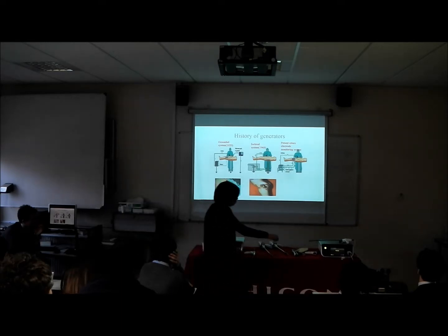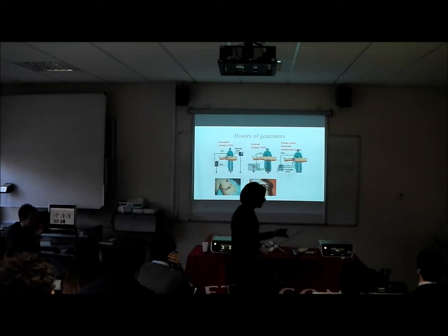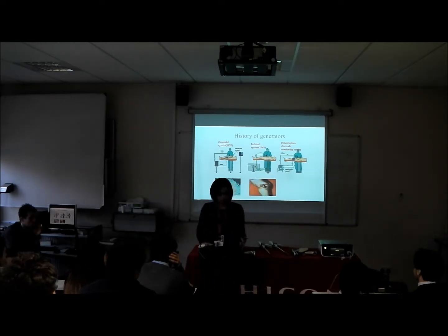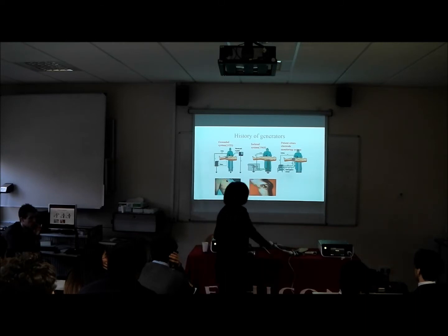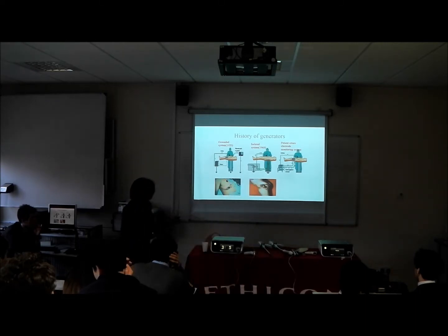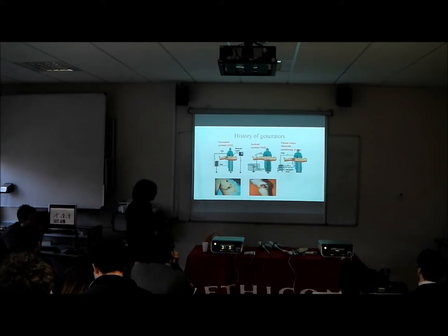That's why the tip of this equipment is really narrow, so that it's precise. Let's say you want to burn this area, you just attach it here. So the current flows through here, goes to the equipment, to the organ wherever you want to cut or coagulate, and then it travels through the patient's body into this patient return electrode, and then back into the circuit.